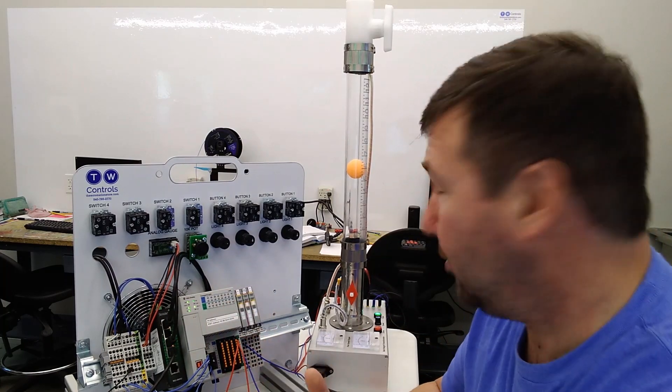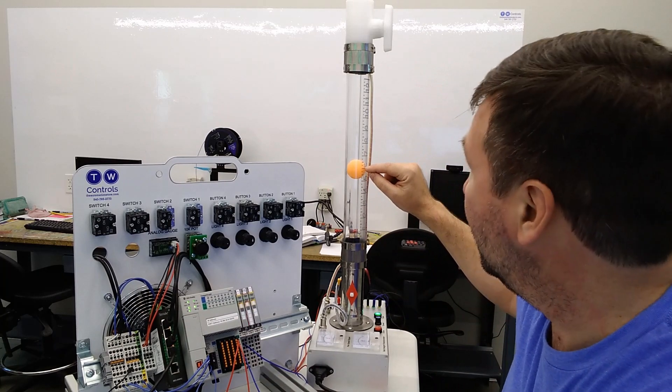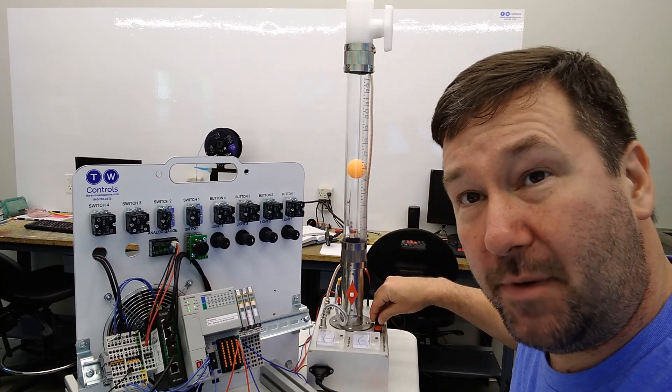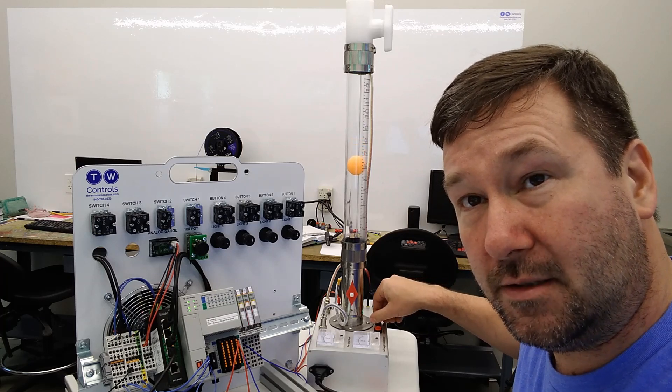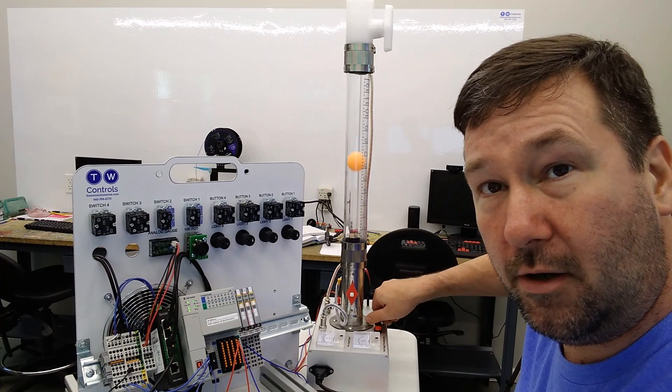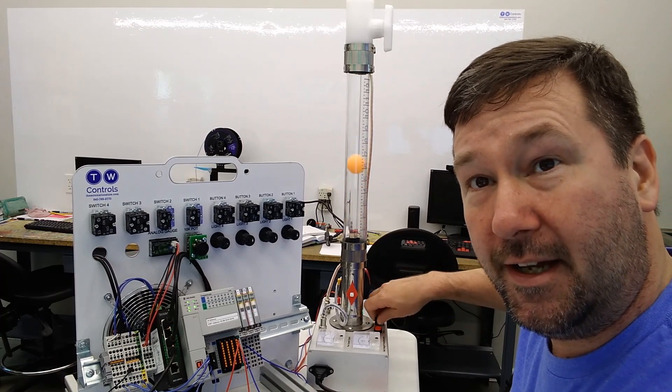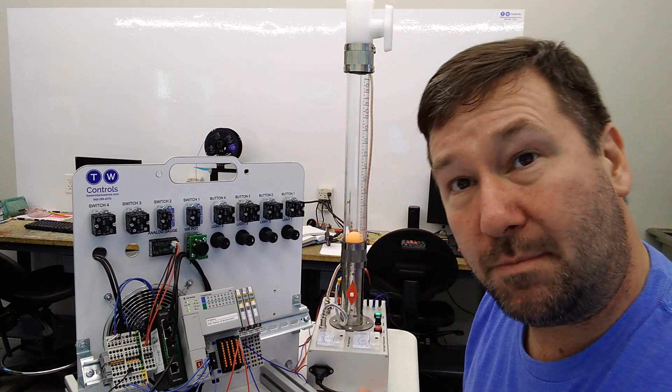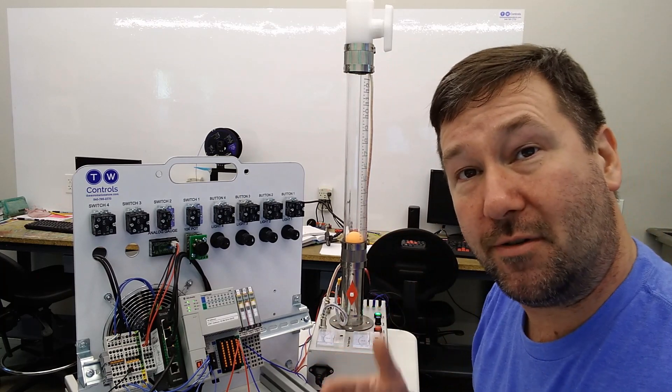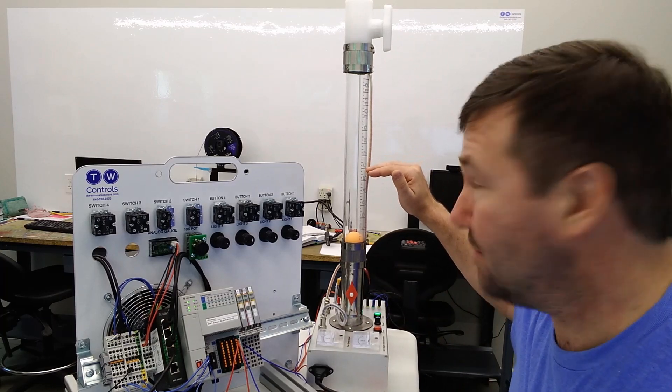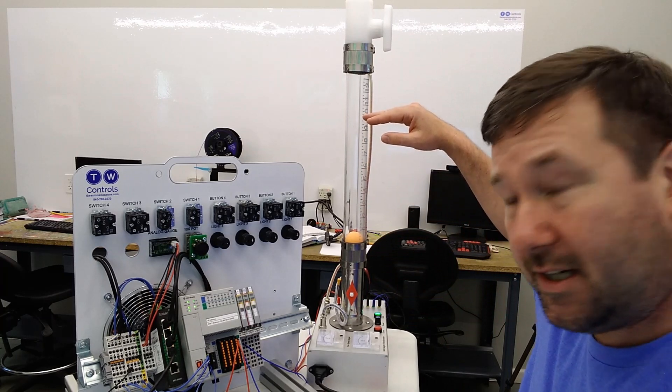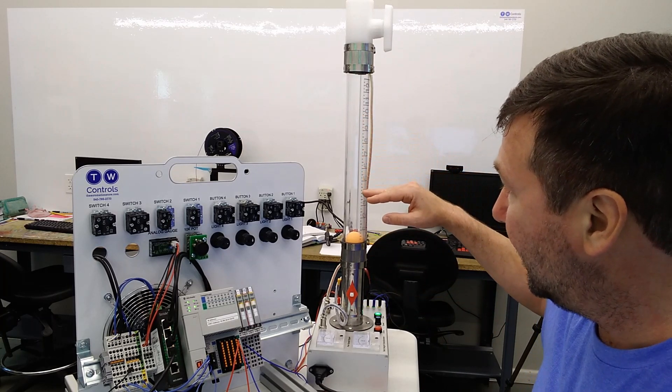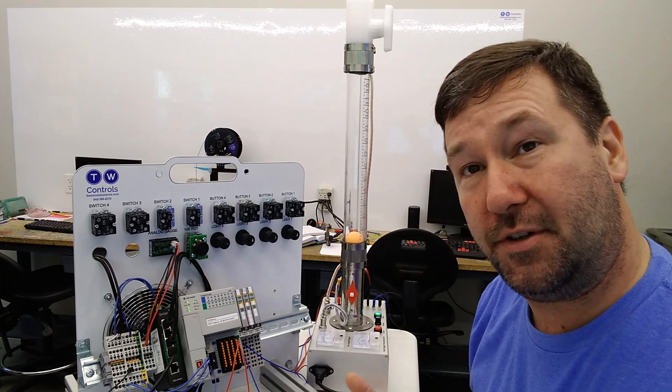For this, what we're going to be doing is we want this ultimately at the six-inch mark. But instead of having it where we can vary our speed a little up and a little down, we're going to have it where it's off, on, off, on. There's a lot of applications for this. Probably the most popular one is a water storage tank. Water storage tanks don't sit at a specific spot. They have a pump, and it'll pump them up to a full mark. Then as you use water, it'll go down. When they get to a low level, they kick on again. That's what we're going to do.